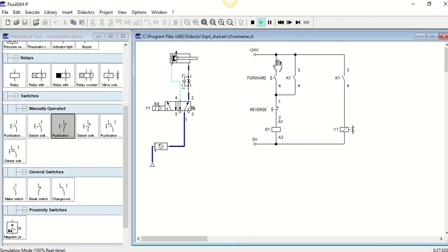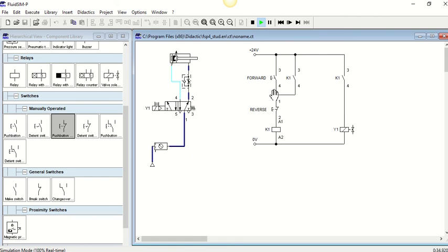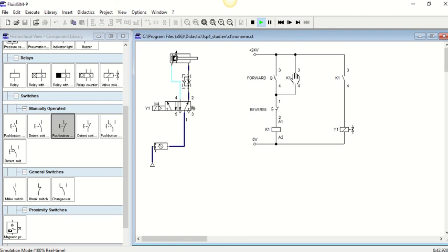So that is the idea of a latch. It always looks like this. You have your kind of start condition to start the latch. You will latch on your relay, and then your relay will be fed back in on itself here. And then in between the relay and where it is fed back in, you will have the break part because that is going to break any supply from either of those pathways that you can get there. So this will always be the same kind of setup, which obviously you will be using maybe a different relay or different buttons or sensors or whatever it is to operate it.